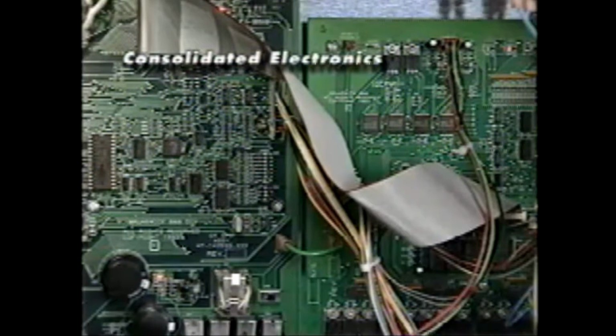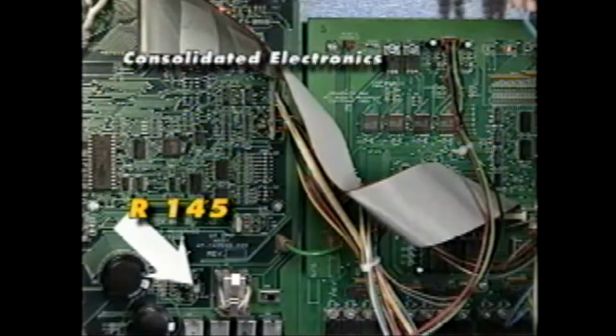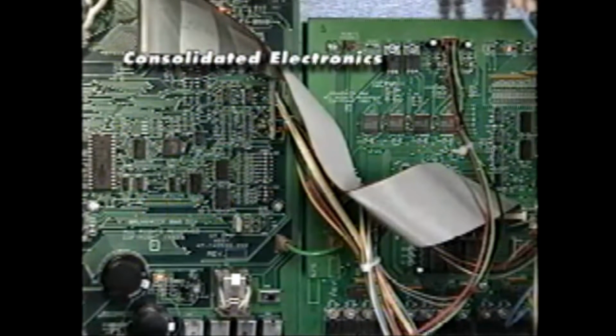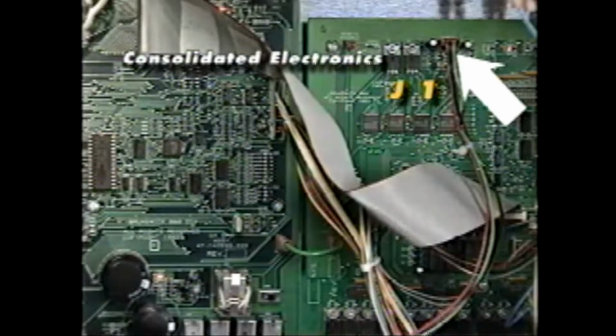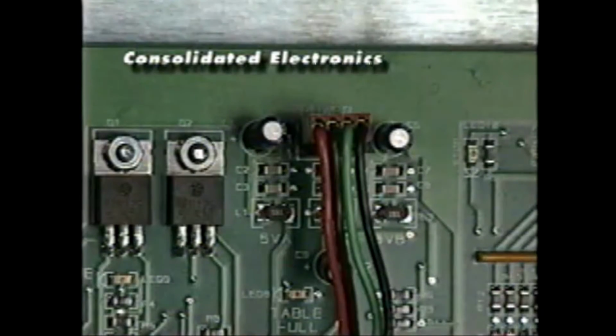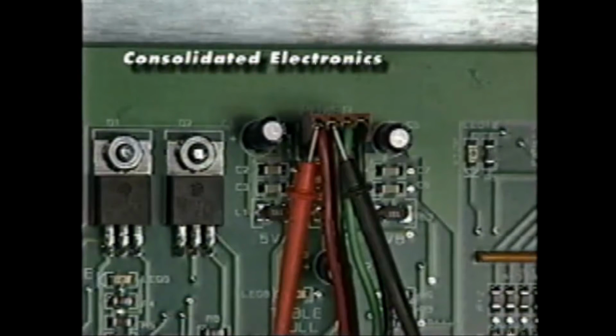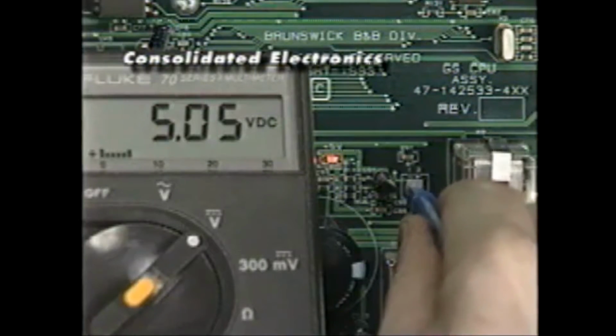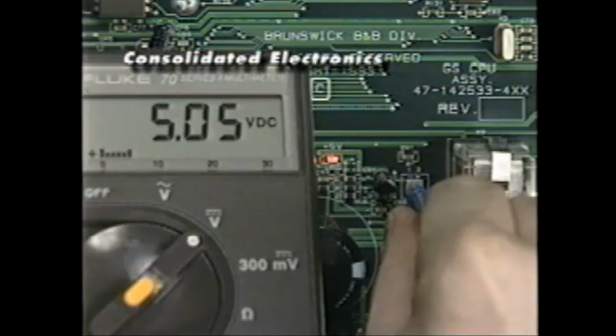The 5-volt adjustment on pin setters with consolidated electronics is made at R145 on the low voltage CPU board. The reading is taken at J1 on the top of either of the two low voltage I/O boards. Connect the meter leads to pins 1 and 2 on the left side at the J1 connector. Adjust the pot at R145 until you obtain 5.14 volts.